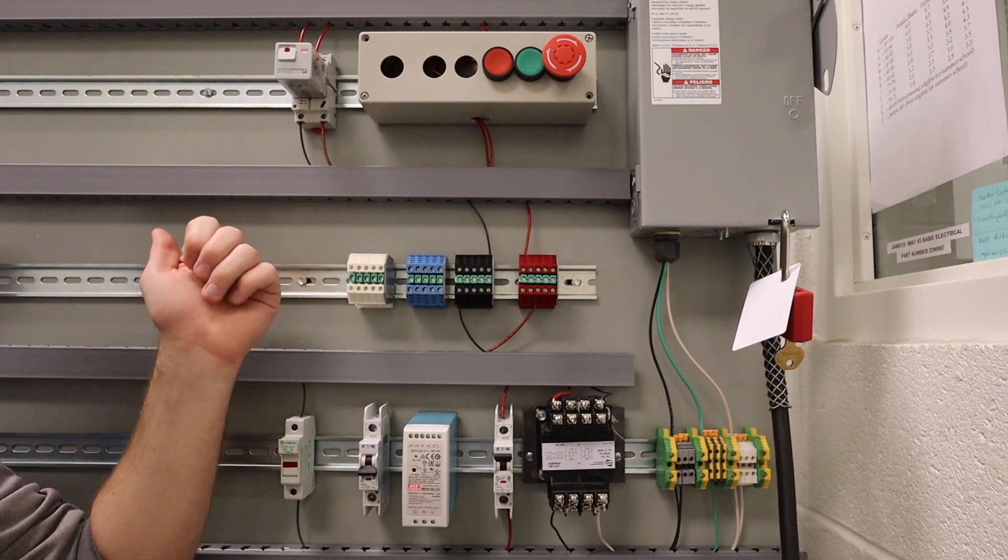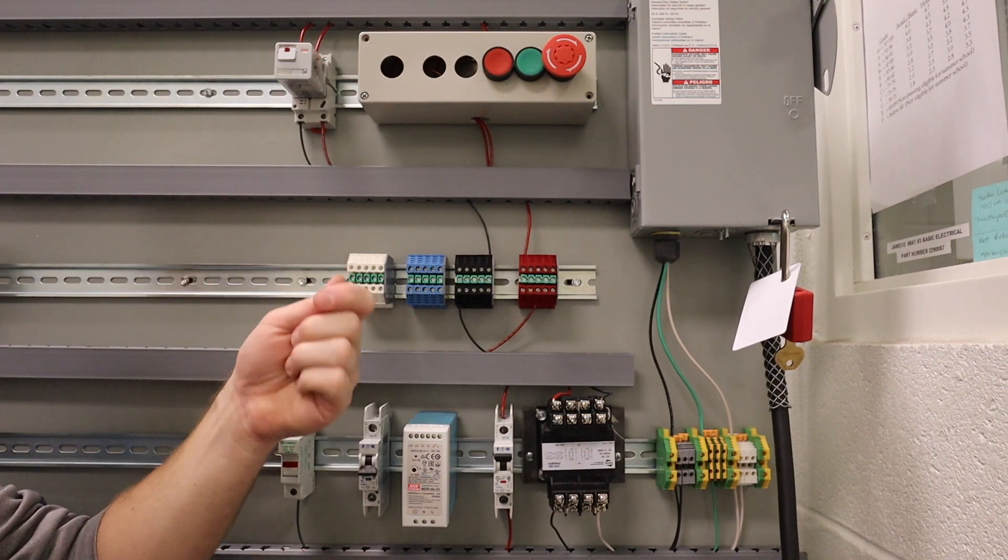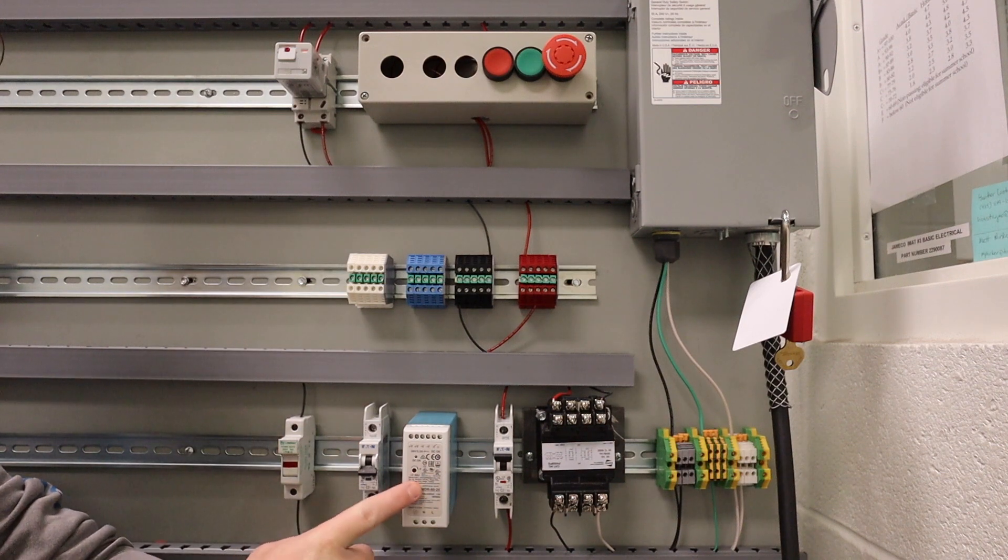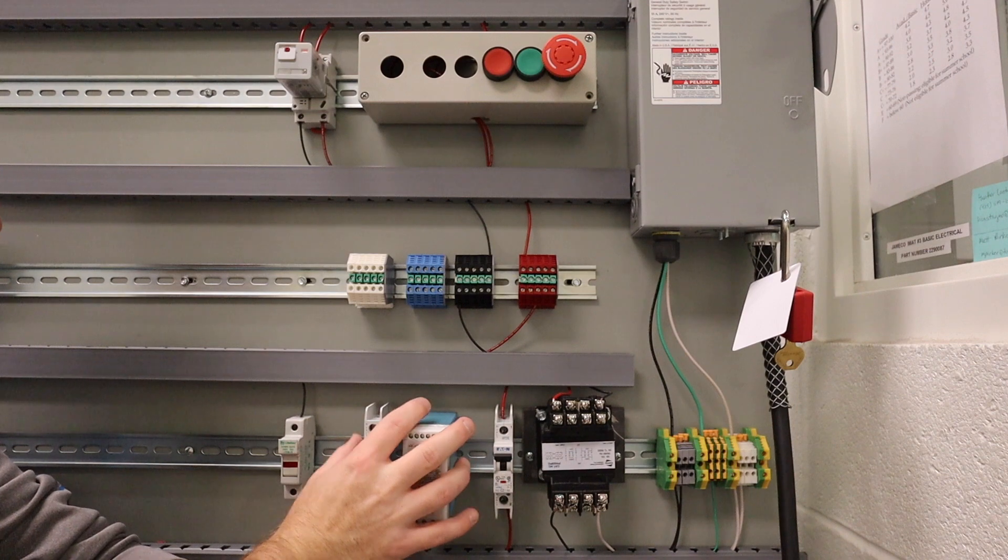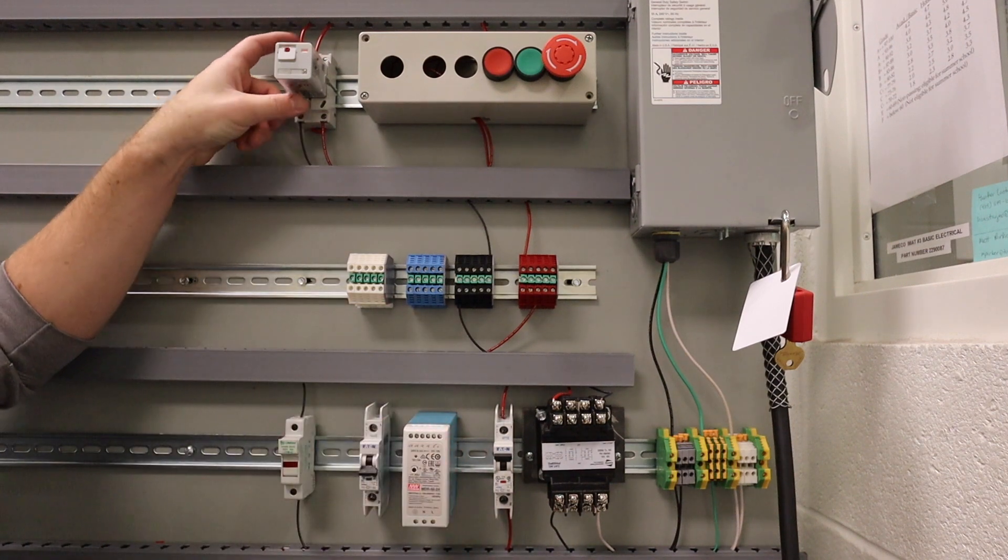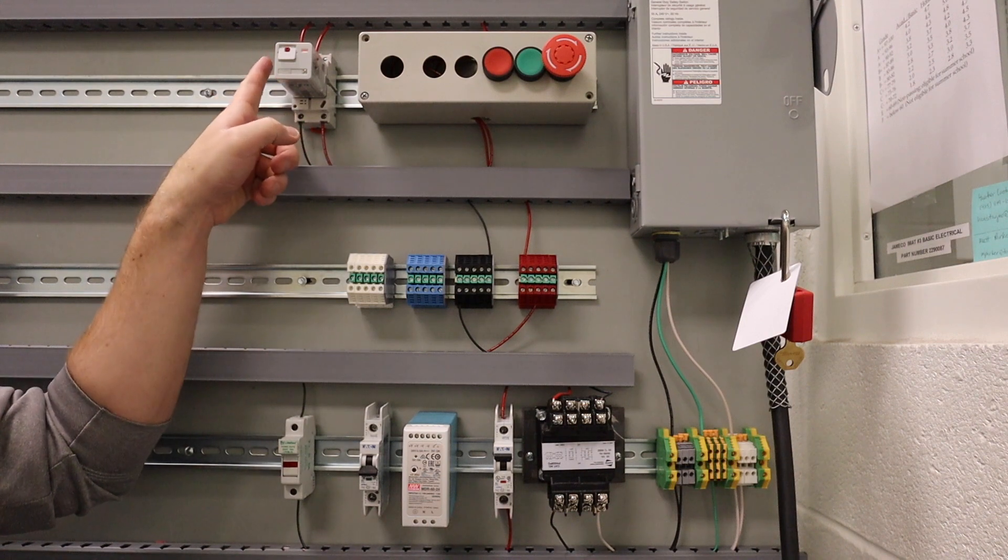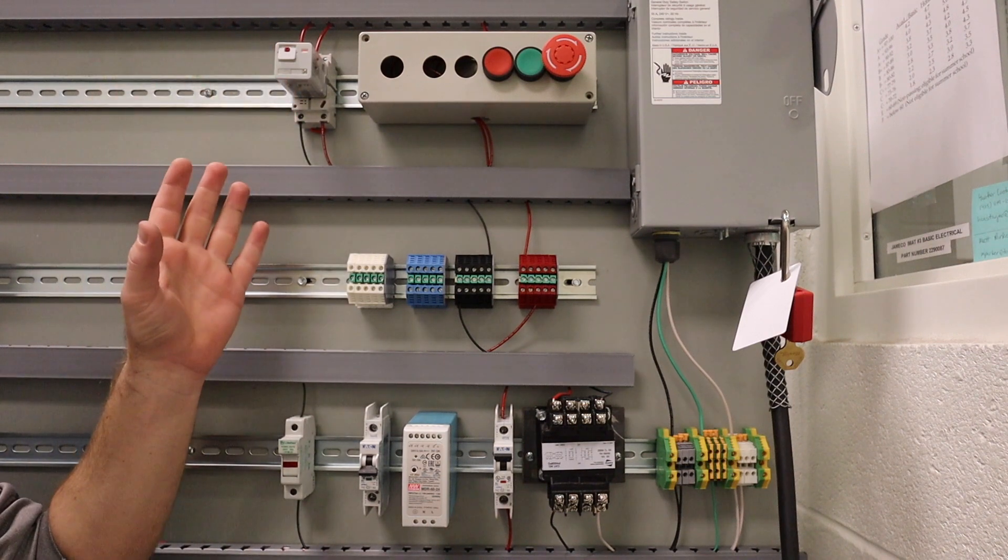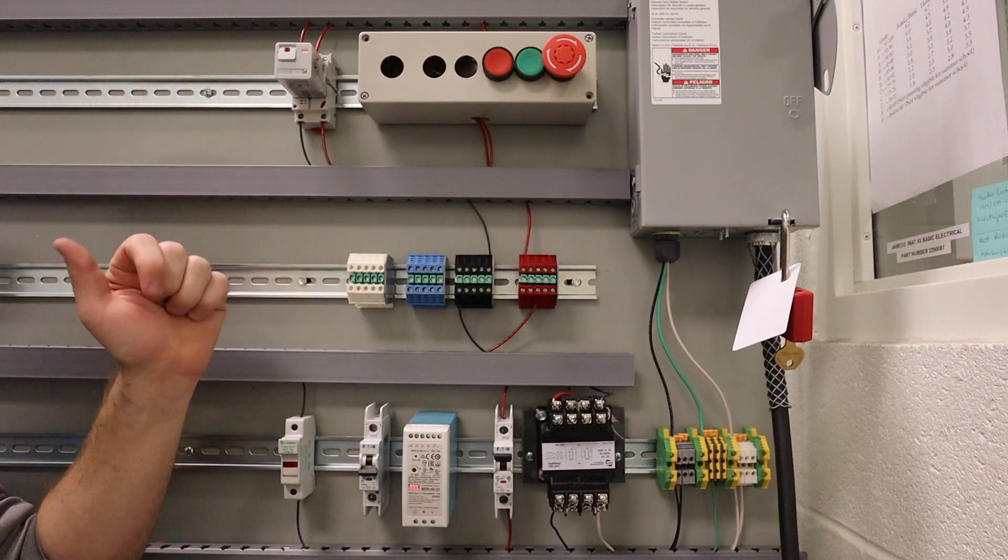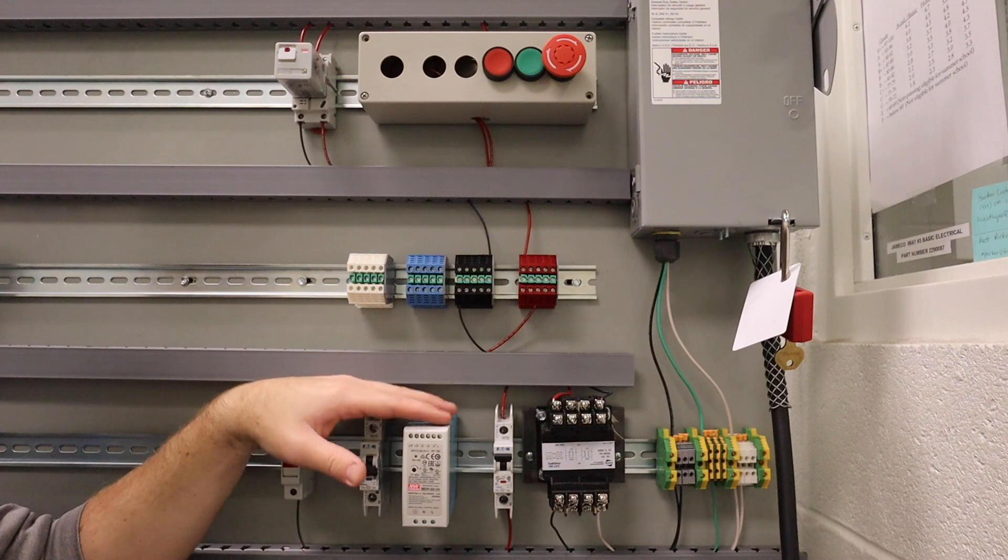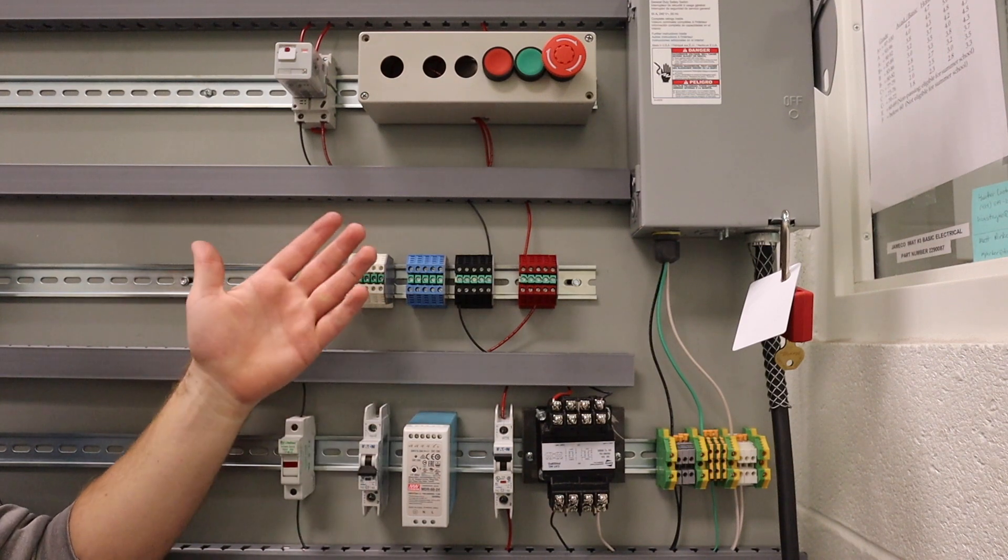One very important thing is this is not connected to the PLC in any way. What we are going to do is come down to our AC to DC converter down here, and we're going to hook all this up. The outcoming power is going to be forced to run through another contact in this relay. I'll show you that in the next video, but that's really all it's doing. It's a totally separate circuit, and all it does is kill the power to our inputs and outputs.